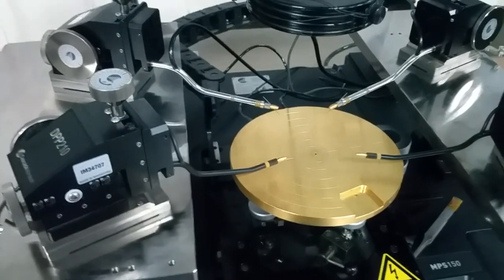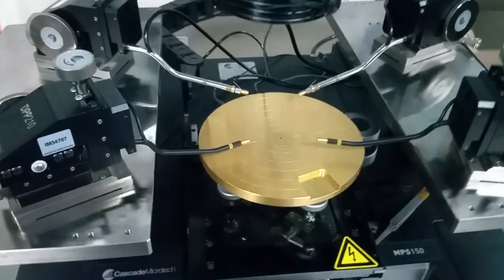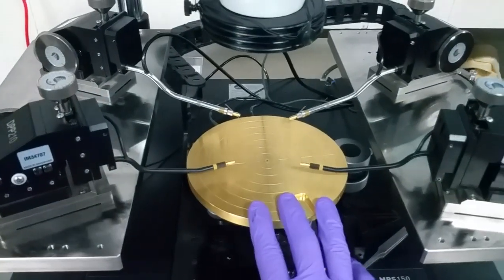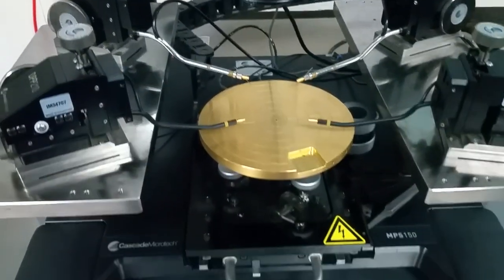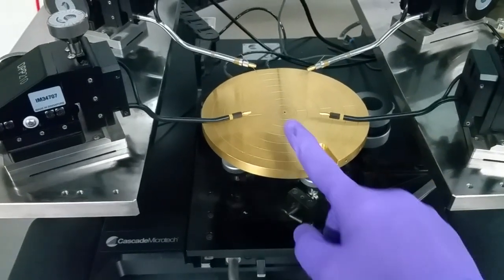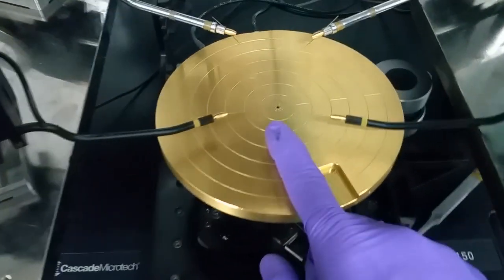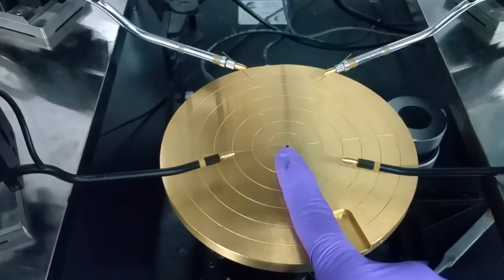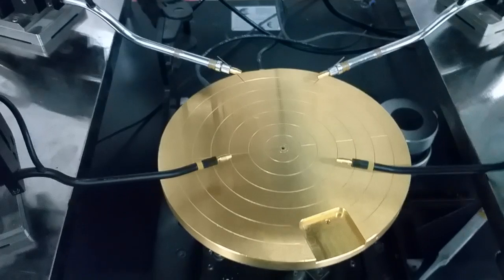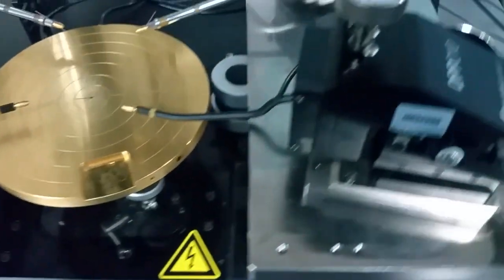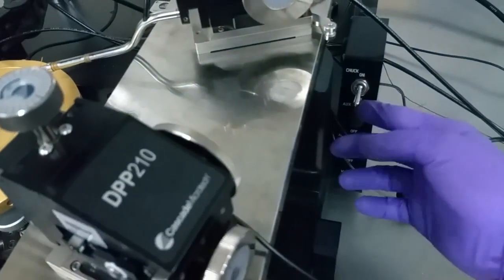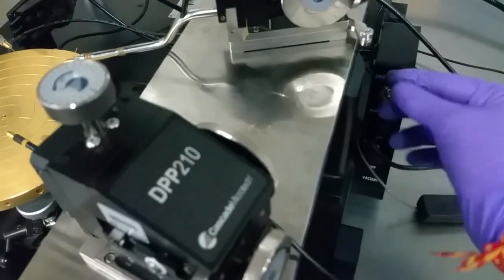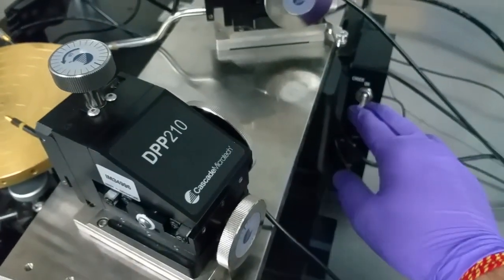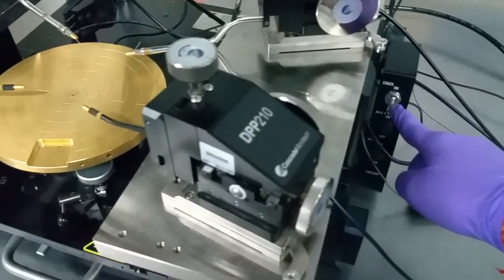So the first step during your device characterization is to put the sample on this chuck. This is a gold plated chuck. When you're putting the samples, you should keep this knob down, and put your sample here in this center portion. This is used to hold your sample. It is further connected to a small vacuum pump which holds your sample. First you keep your sample here, then here is one knob, chuck on, off. If you put it up, then it will hold down your sample. And then you should turn it off when you want to remove it.